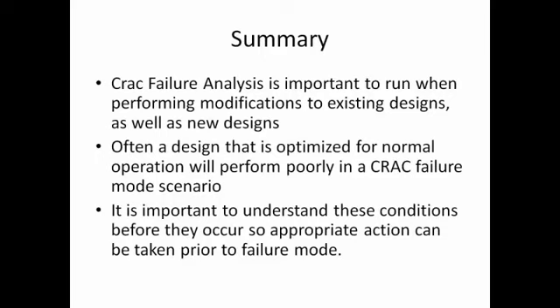But today our primary mission, I think, was to point out that just because the design says N+1, just because you have N amount of cooling in kilowatts or tons or whatever that's beyond what you need today, doesn't mean you're going to be safe in an operational state. It's important to understand the failure modes and what they look like, both in terms of optimizing the data center for operations day to day and also understanding what happens in a maintenance mode or a failure mode. And having a tool like this allows you to understand that.